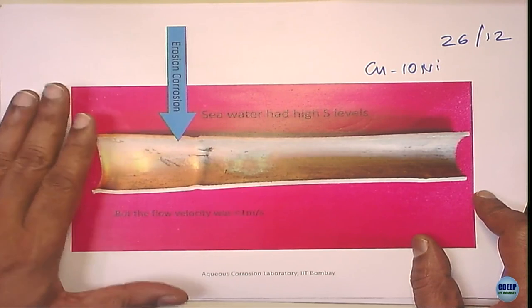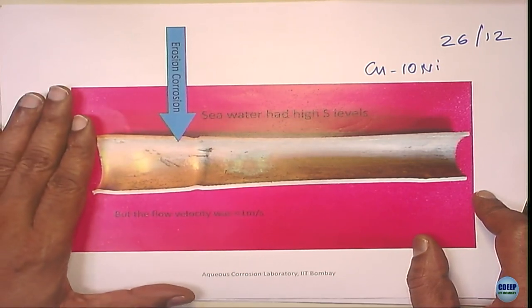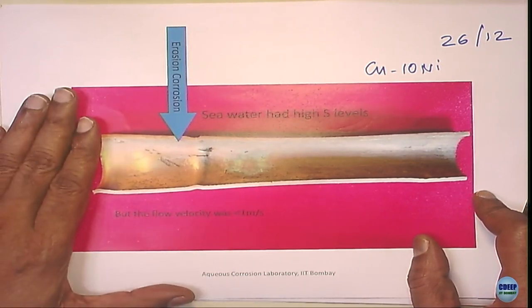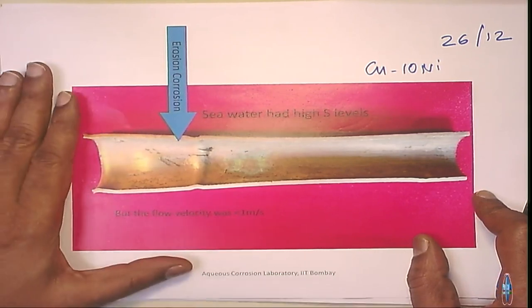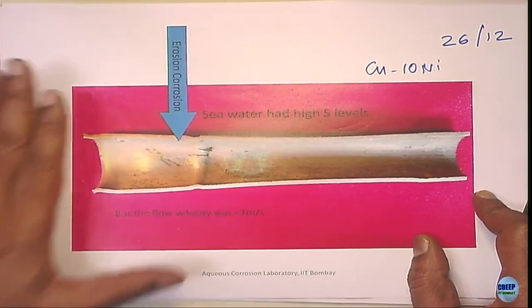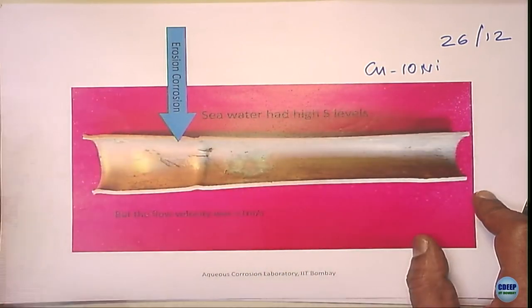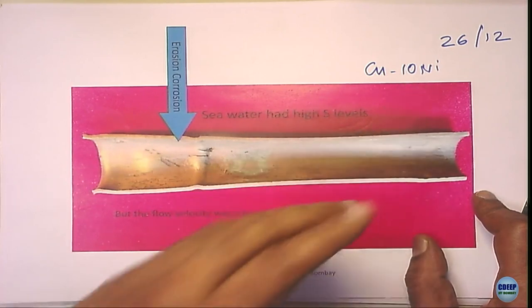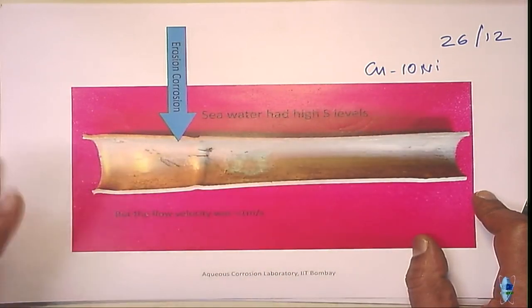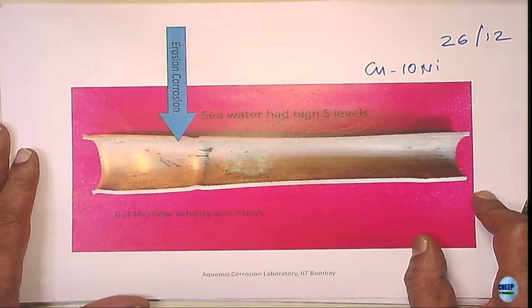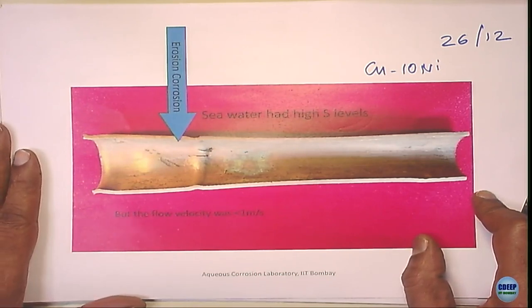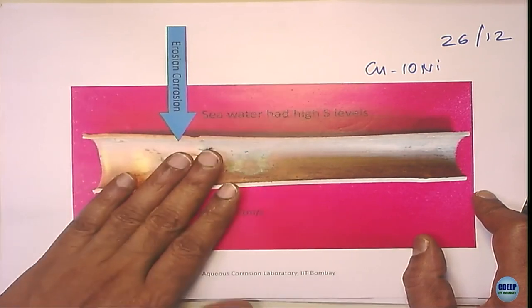So if you wrongly diagnose it, you have a problem. Finally, we went for higher nickel. We convinced the people to go for nickel, and the tube did not fail for 3 to 4 years. Now there are problems here: when you say go for copper-30 nickel, there are two issues. If you are de-alloying, that's one problem. Not only that, going to 30 nickel, what is the cost of it? The cost is so high, increased nickel costs quite a lot. So you run the risk of failure by spending more money if you wrongly diagnose it.